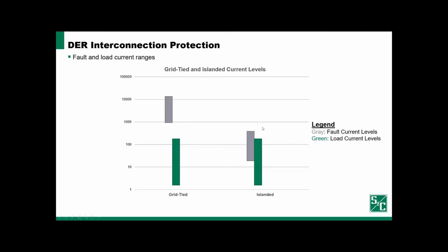If you look over at the part of the plot on the right, you can see that fault current levels and load current levels are overlapping. The fault current can vary significantly based on what resources are online and supplying the load at any given time when we're separated from the bulk system. And in some cases, with low amounts of generation online, the fault current can be less than the load currents when higher amounts of generation are online. This can obviously challenge the use of overcurrent protection and make it impractical to use solely overcurrent protection in microgrid applications.